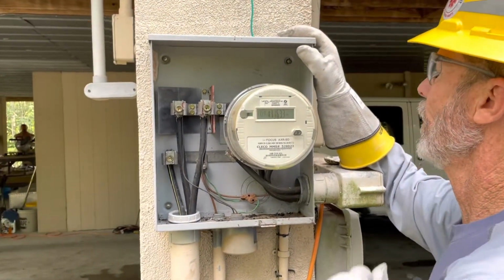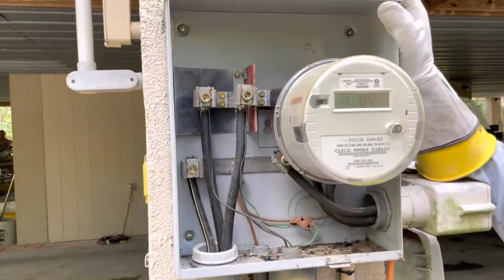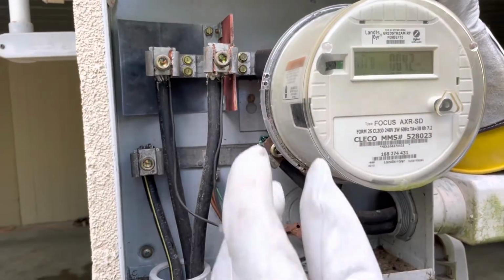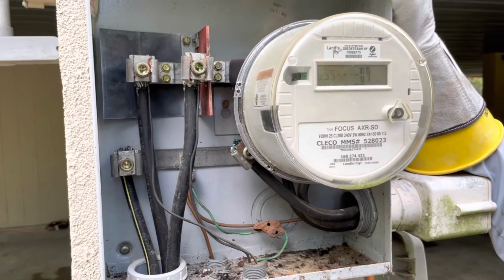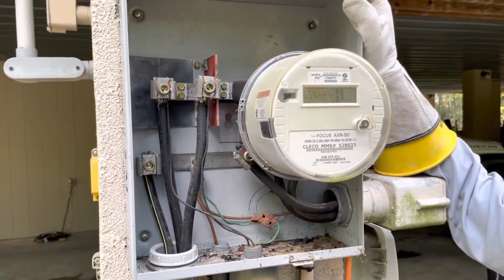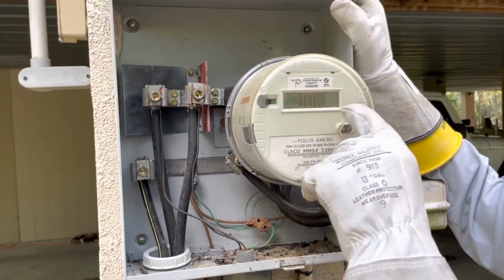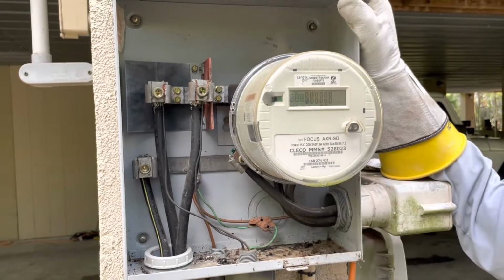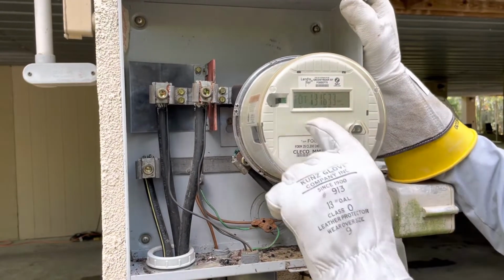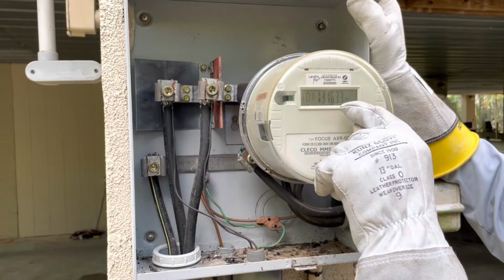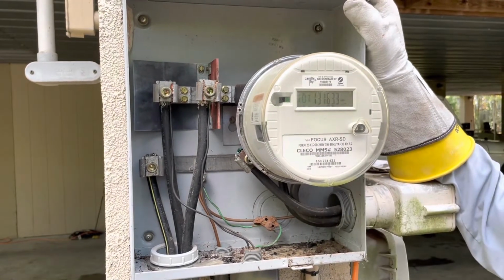So look at the condition of the lugs, view the overall condition of the pan, and then look to see what kind of load is on the meter. If the disc is going really slow, you're not going to pull an arc. But if the disc, the little line on the bottom, is moving quickly, you're going to pull a hard arc.